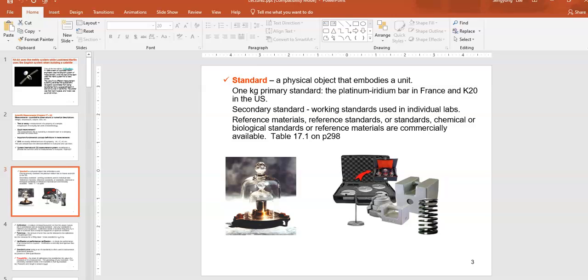If that standard comes with a certain weight, let's say it's a 500 gram standard, if your instrument, your balance, is doing its job, it should read very close to 500 grams. If not, then there's a problem with your instrument, the balance, at the time, right? So standards are used for that function. It will measure your instrument against the defined unit. If there's a gap between the defined unit on the standard and what your instrument is measuring, there's a problem. You have to go through a calibration process to fix that, right?